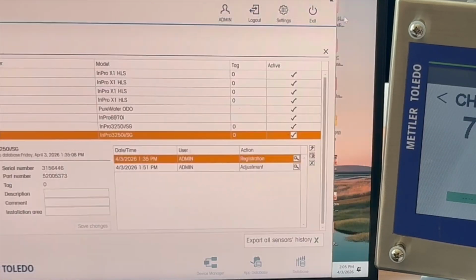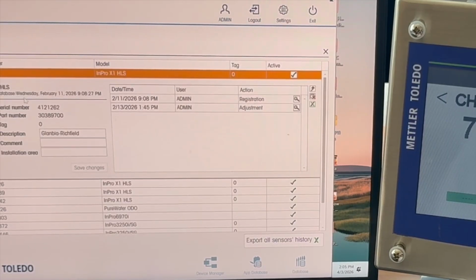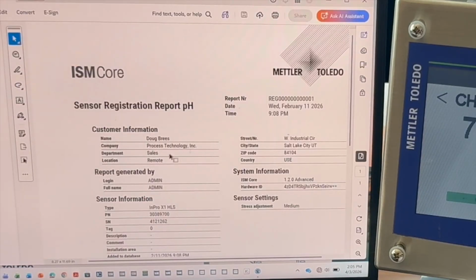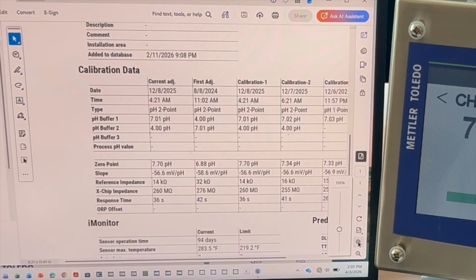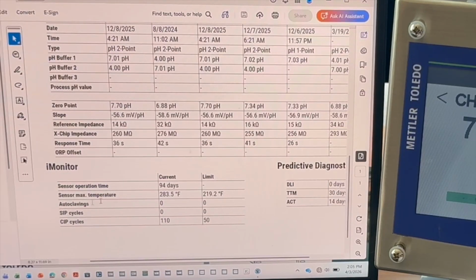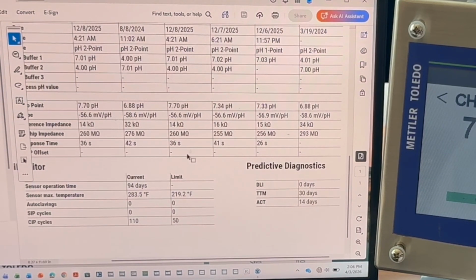It's all provided automatically. Let's look at an example of another sensor that actually had an interesting finding. The customer didn't realize they had a temperature excursion. So if we zoom in a bit here, here's an example where down here where it says sensor max temperature, what was captured was a temperature that exceeded the limit of that sensor. This sensor doesn't handle these high temperatures, and they actually exceeded it and they didn't realize it. But this was a way for this program, or the sensor and ISM technology, to automatically capture that. The sensor was in operation for only 94 days, and surprisingly, the DLI was reading 0 days. There were a lot of other issues with this sensor. We had a relative change in our impedance values, but mostly that high temperature is probably what determined that this algorithm was killing this sensor and showing 0 DLI days.